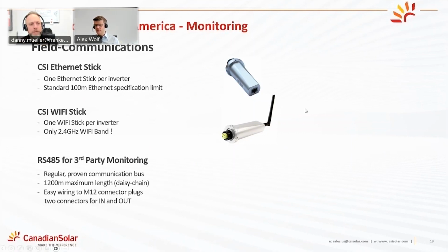Any recommendation between either? It really depends on how the system is set up. The RS-485, if you already use a third-party monitoring, then you can certainly use that. If you want to use the monitoring platform from CSI, which is quite powerful, and we will have a separate webinar about that, all the features, then you need to have one of those two first options, the Ethernet stick or the Wi-Fi, because that is the gateway that relays all the information from the inverter to the portal and also executes commands that you are sending from the online portal to the inverter if you want to use, for example, IV curve tracing and parameter settings, firmware updates, and whatnot. Next page.